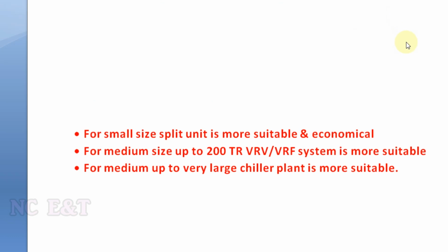To summarize, for a small size building, a split unit is more suitable and economical. For medium size up to 200 ton, VRV and VRF system is more suitable and more economical. But for medium up to very large, a chiller plant is more suitable.